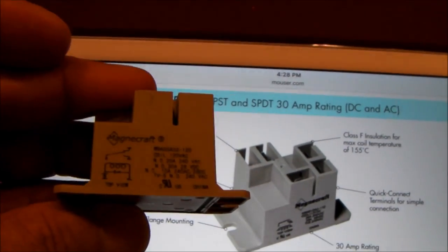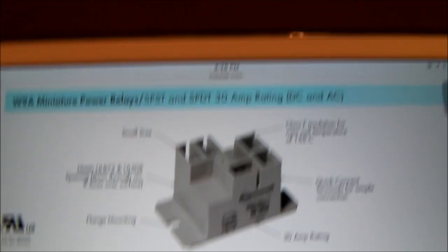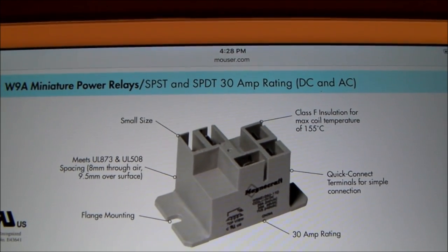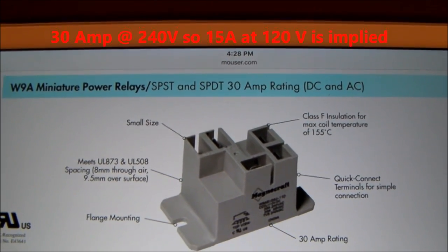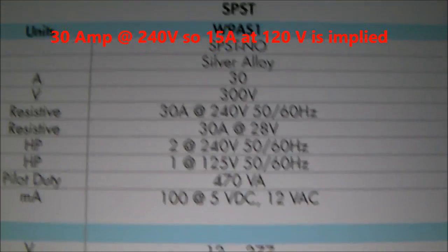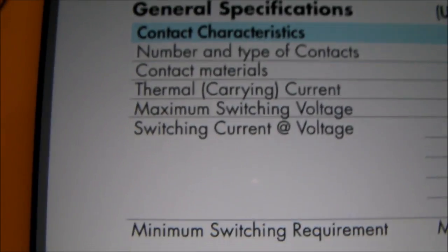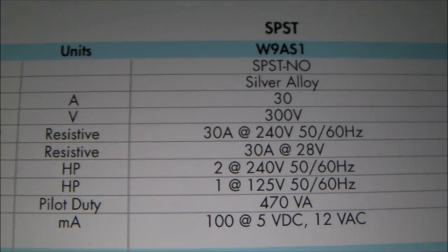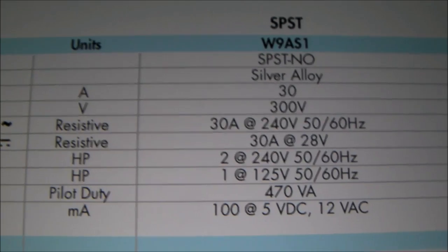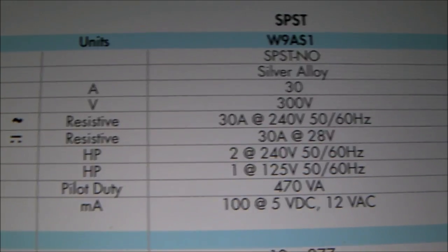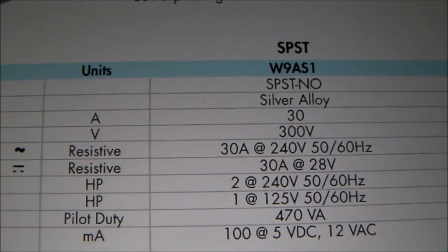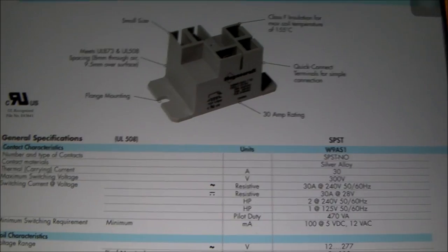So here's the spec sheet for this relay. And you see it's a 30 amp rating, but right here you can see that it has a switching current at voltage. And you can see it says 30 amps resistive load, horsepower, two horsepower at 240 volts, one horsepower at 125. So this relay is plenty hefty enough to be able to control up to a one horsepower pump.